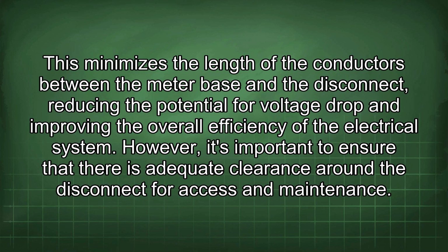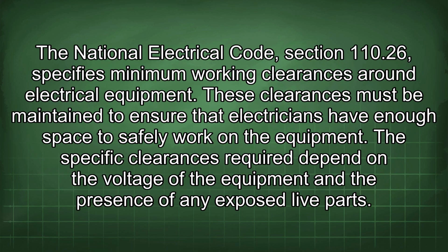However, it's important to ensure that there is adequate clearance around the disconnect for access and maintenance. The National Electrical Code, Section 110.26, specifies minimum working clearances around electrical equipment. These clearances must be maintained to ensure that electricians have enough space to safely work on the equipment. The specific clearances required depend on the voltage of the equipment and the presence of any exposed live parts.